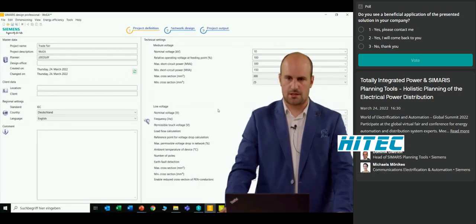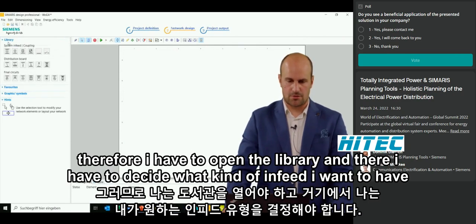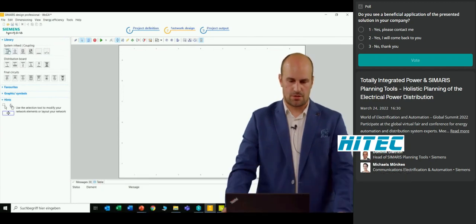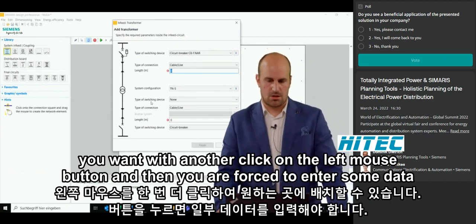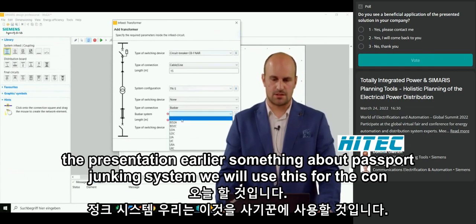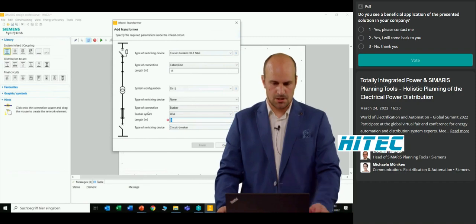I can go back to project definition to change or edit everything we selected earlier, but now we want to start to create our network. I open the library and decide what kind of in-feed I want. I start with a transformer. After clicking the transformer, you place it with a left mouse button click, and then you are required to enter some data. Some values are pre-selected and some have to be entered by you. The medium voltage cable length will be 15 meters. We'll also change the system configuration to use a busbar trunking system for the connection of the transformer with the main low-voltage switchboard.